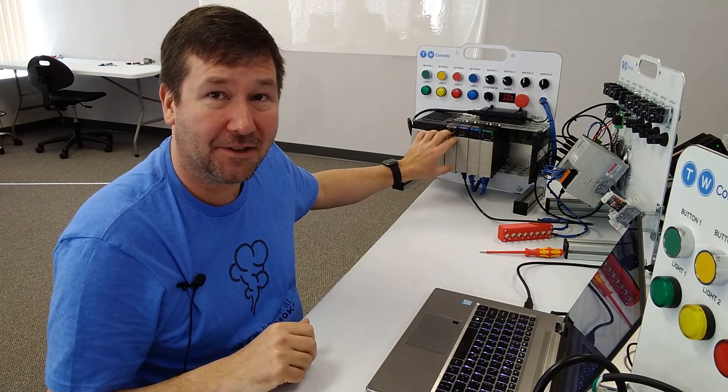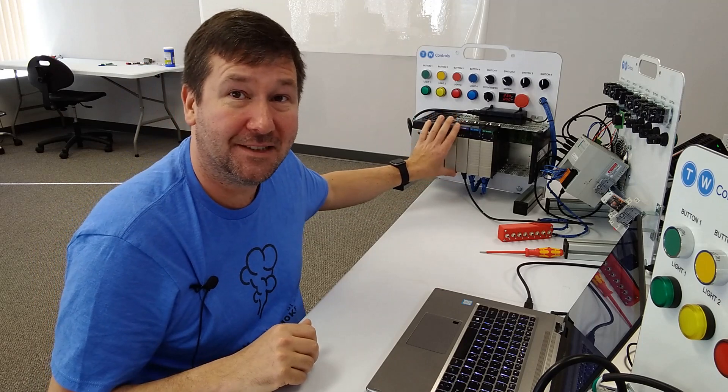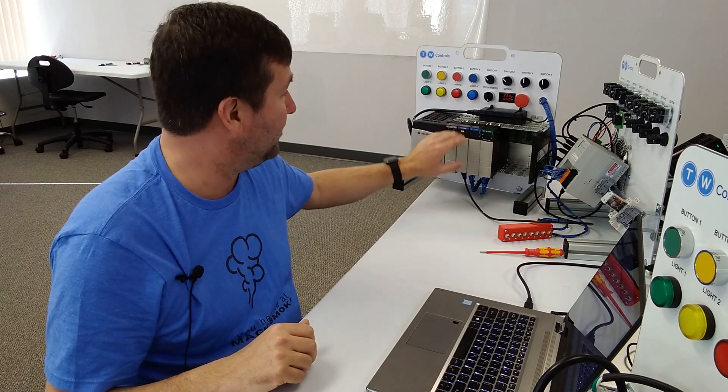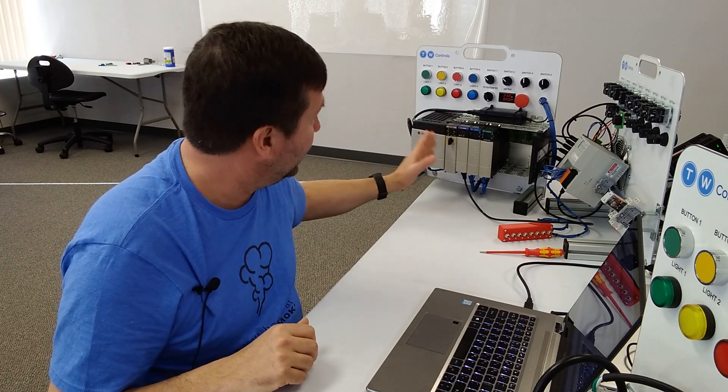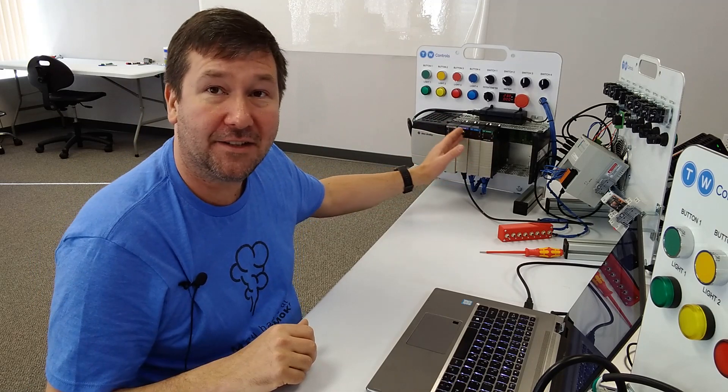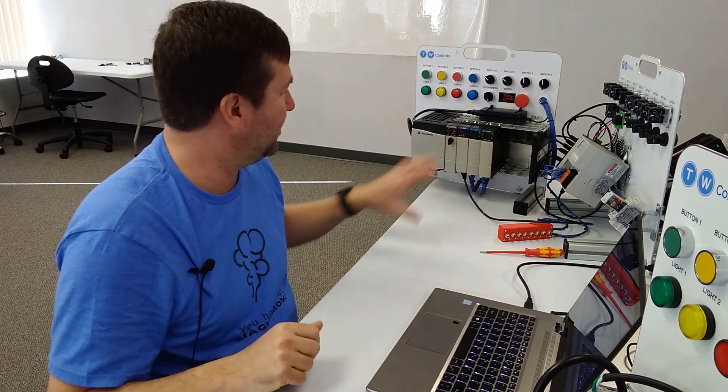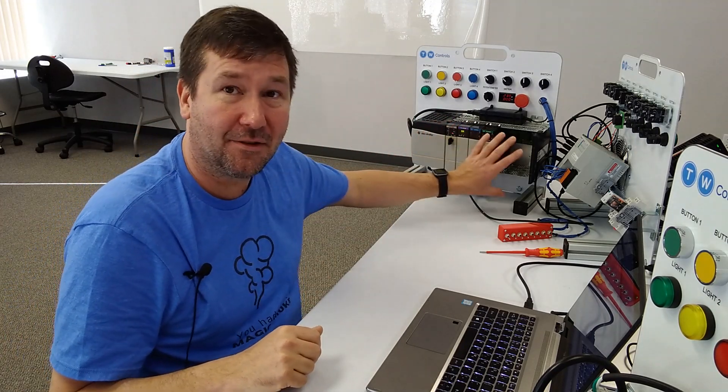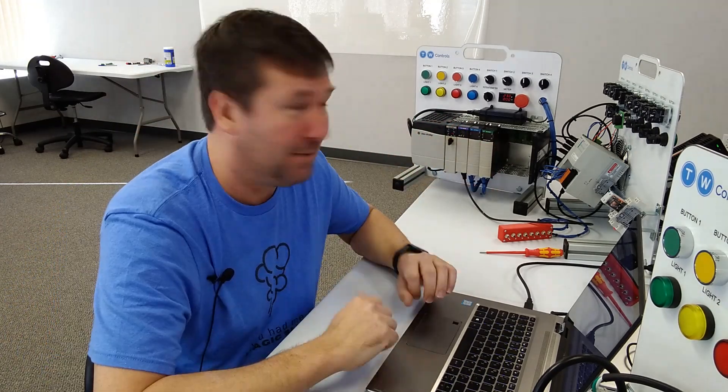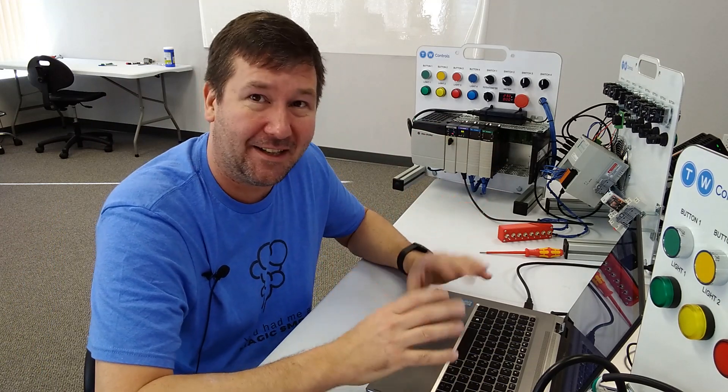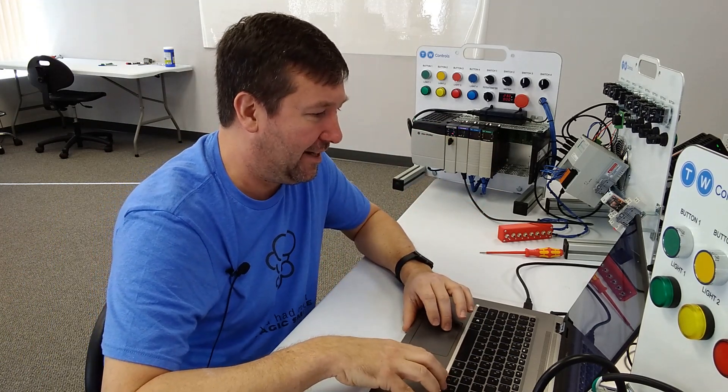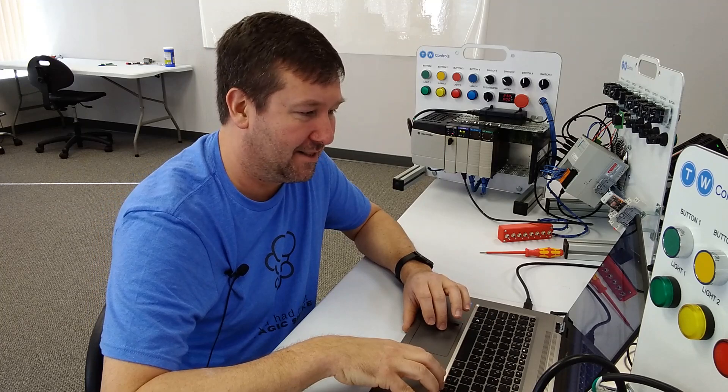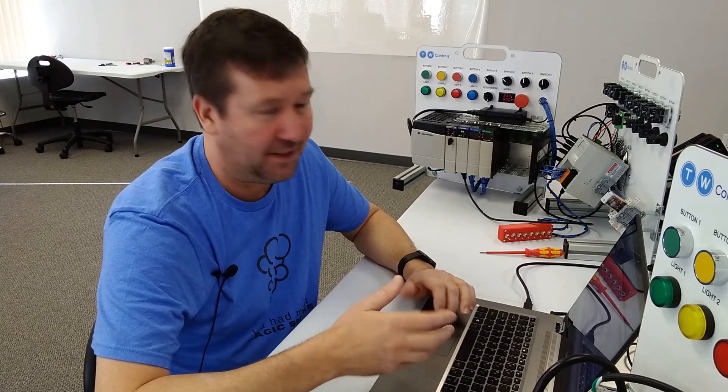even though it has a processor in it that we would think is controlling all the modules. Also, I've got this faulted right now for another video. If it was not faulted, if it had an IOK, you'd see all OK lights through here. So mentally, you would think that this is controlling all of it. But this is something I ran into somewhere. So it's something I like to bring up is you kind of need to pay attention sometimes to what is in this IO configuration over here.